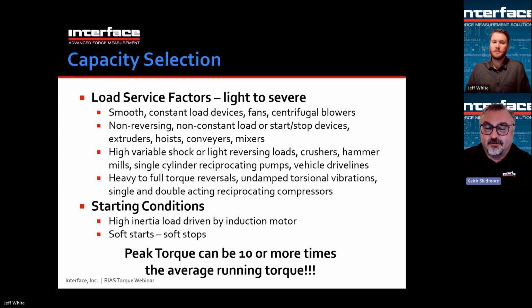And we've had customers who have ruined torque sensors and say, well, what happened? No, nothing happened. It was running great, but somebody hit the emergency stop. And that may be good. If you have to hit the emergency stop to save somebody from getting hurt, great. But it shouldn't be used as a standard stop method because it can be damaging. Note, peak torque can be 10 or more times the average running torque. So you have to figure out what the peak torque is going to be and size your sensor appropriately.